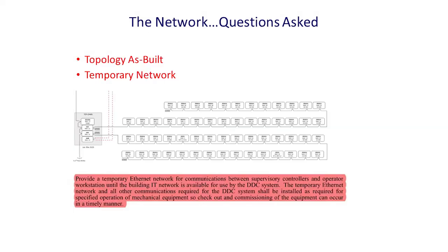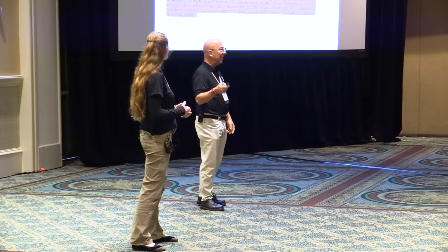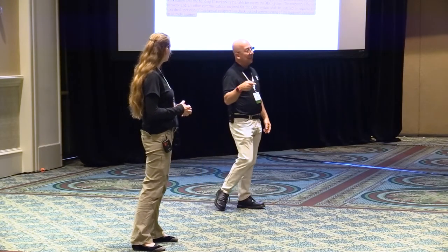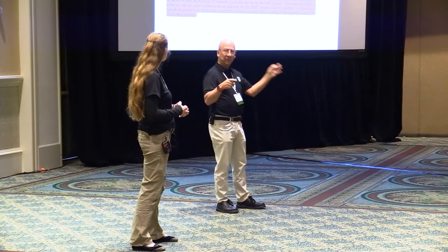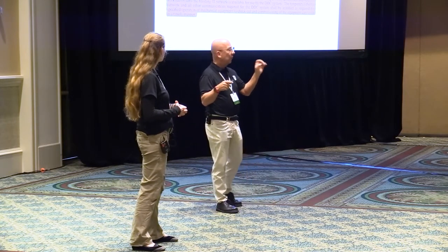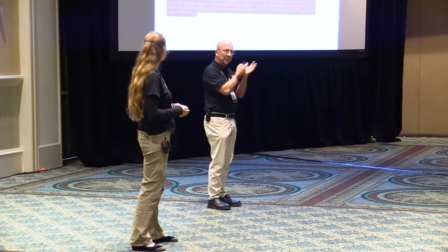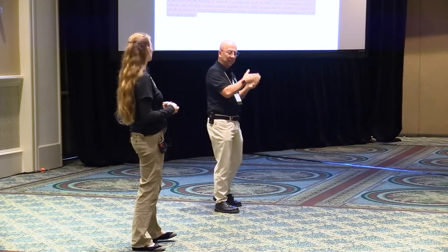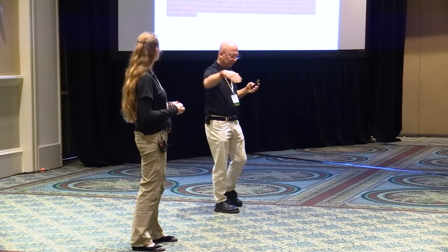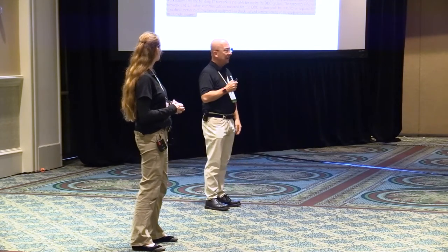So then the other portion, the as-built drawings. I always think that this is the applications engineer's best shot at thinking how it's going to get wired. During our meeting, we're going to be calling them on it, saying we're going to want to see an as-built topology drawing, and we're going to want to break your system by disconnecting the BACnet system to see that we're expecting all of these devices from here on to go off, and those types of things.